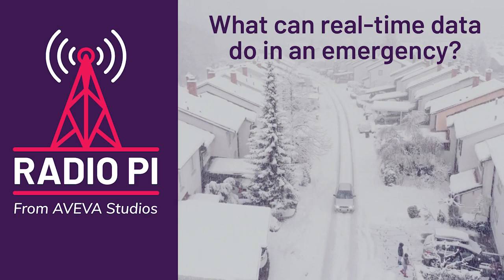For water and electricity, that was actually really straightforward, since it's well understood from an industrial standpoint. For the water meter, we put in a non-contact meter that detects the spinning metal inside, because every spinning piece of metal makes a bit of a field, and that field cycles at the same rate as your impeller. So you can use that to back out how much water you're using in real time — that's exactly how our meter works.